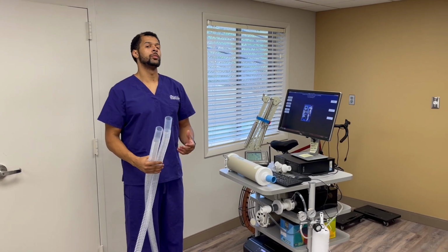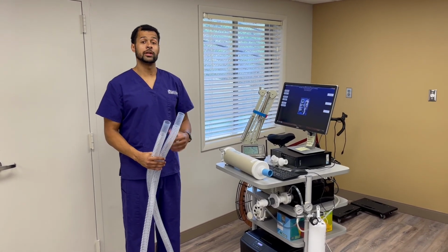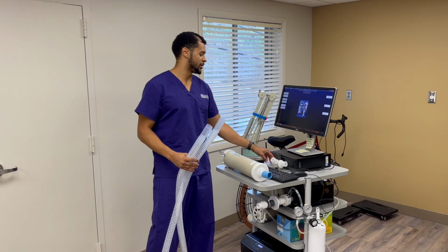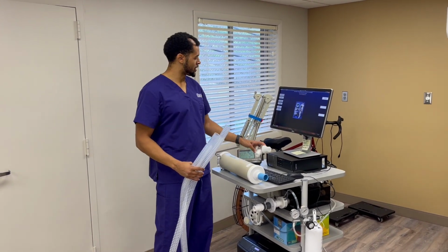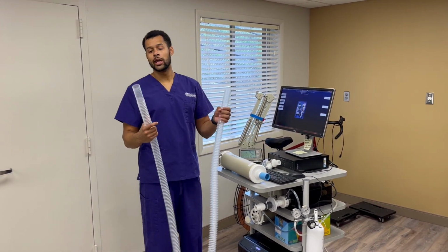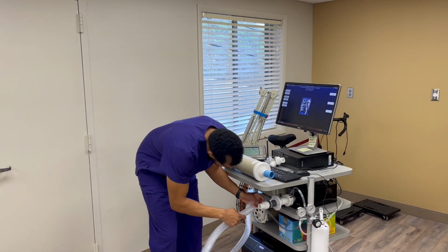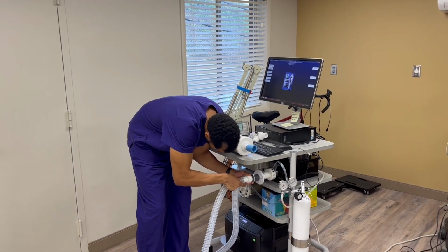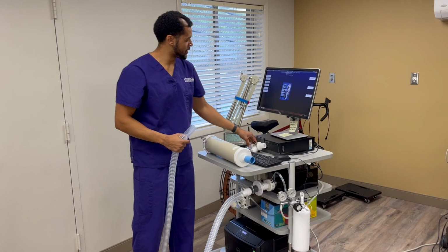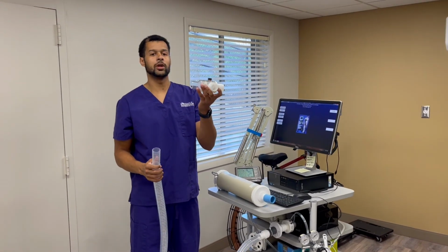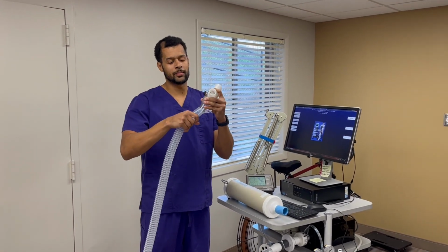Next, we're going to do the flow meter calibration. At this step, you should have already done the gas calibration. You should also have already made your mask. So the first thing you're going to do is take your tube and plug one end to the mixing chamber right here, and the other end is going to go onto your mask. So you always plug the clear part onto the clear part.